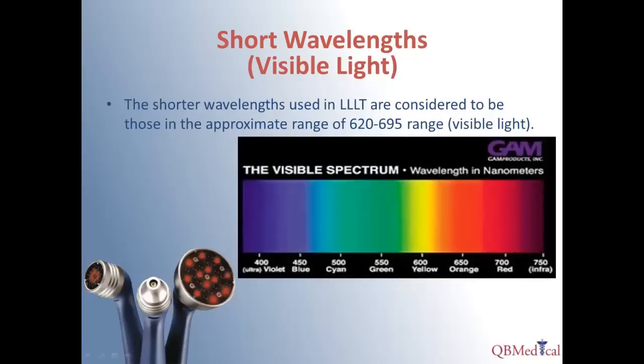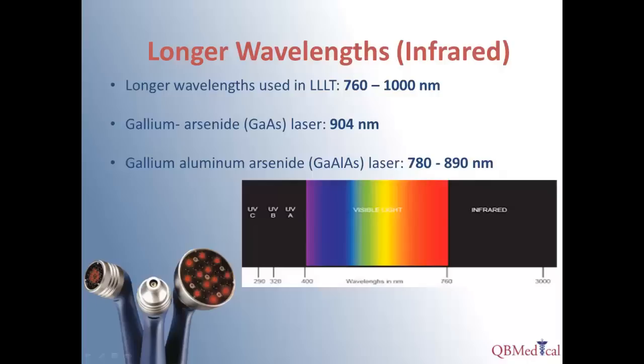The wavelengths in the lower end of the therapeutic spectrum are in the higher end of the visible spectrum, giving us red light. As we get into the longer wavelengths used in therapy, we approach the near-infrared to infrared end of the spectrum, meaning these lasers are invisible. The gallium arsenide laser gives a wavelength of 904 nanometers, and gallium aluminum arsenide gives anywhere from 780 to 890 nanometers — two of the more common active mediums found in therapeutic lasers.